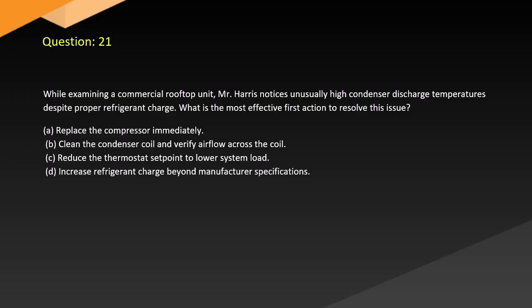Question 21. While examining a commercial rooftop unit, Harris notices unusually high condenser discharge temperatures despite proper refrigerant charge. What is the most effective first action to resolve this issue? A. Replace the compressor immediately. B. Clean the condenser coil and verify airflow across the coil. C. Reduce the thermostat set point to lower system load. D. Increase refrigerant charge beyond manufacturer specifications.